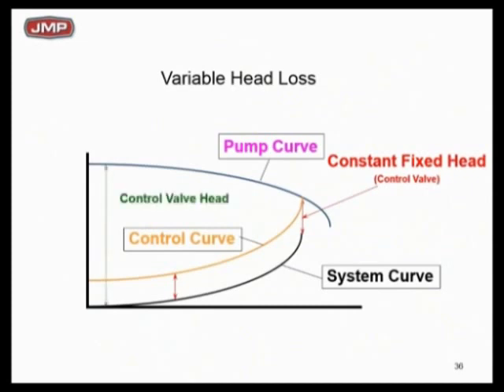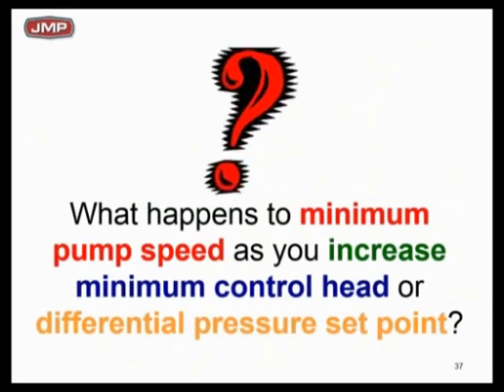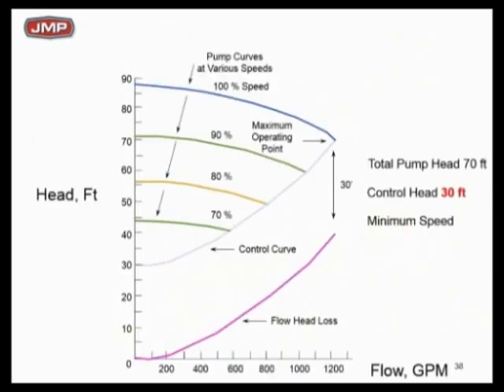That control head — that fixed head — is the one controlling the minimum speed of my pump at shutoff, and it controls efficiencies. We're misleading clients when we say a variable speed drive will fix anything. Here's the big question: what happens to the minimum pump speed as you increase the minimum control head, or that differential pressure setpoint? Let's plot it. I've got a pump selected for 70 feet of head. On this graph, a control head of 30 feet is shown, with the purple system curve — I need to add 30 feet to get the light blue control curve.